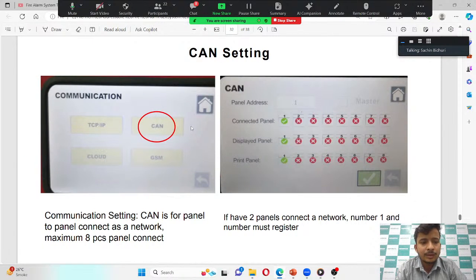Then the CAN bus, as I already told you, is for connecting multiple panels in the same network. In the CAN bus settings, you can enable and disable the panel, or you can provide the panel a different address, because each panel should have a different address. For addressing the panels, you can do it in this CAN bus option. CAN is for panel to panel connection as a network. A maximum of 8 panels can be connected.